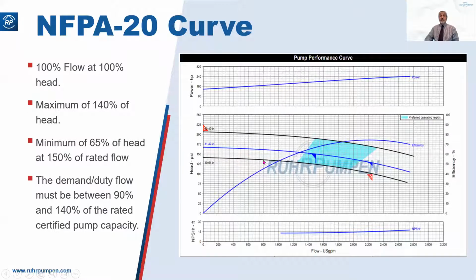NFPA-20 specifies the rated conditions. So here we have one that's 1,500 gallons a minute, for example, at 150 PSI. It also requires that the shutoff head be no more than 140% of the rated head. So here we've marked the 140% condition, and here you can see it's comfortably less than that. It also requires that the pump will run out to at least 150% of the rated capacity at a head which must be more than 65% of the rated head. So here again is the 150%, 65% condition, and you can see we are comfortably above it. So what NFPA-20 is looking for is a relatively flat curve that will give you a wide operating flow at or near the rated discharge pressure.